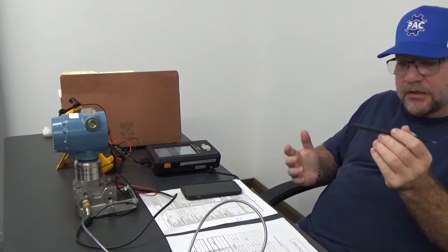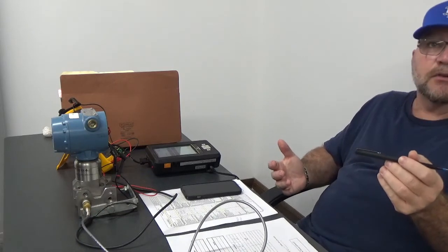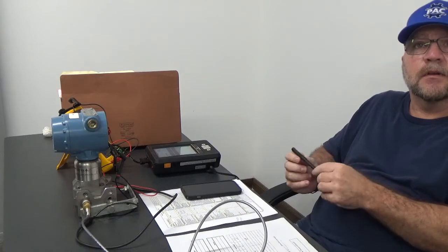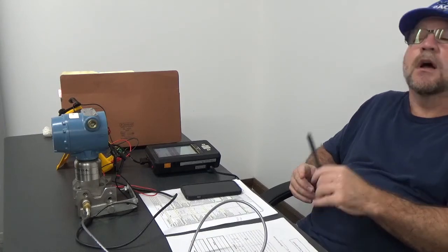So basically what I've done is take my span and multiply it by 25, 50, 75, and 100. What's your span? 143. Okay, yes, that's exactly what you do, Tom. You take your span and multiply it times 0.25, 0.50, 0.75. That should tell me what my pressure should be at 25%. No, but you have to add 2 because you have to add your zero. Your zero value is 2. That's right. If you don't add 2, it won't be right.